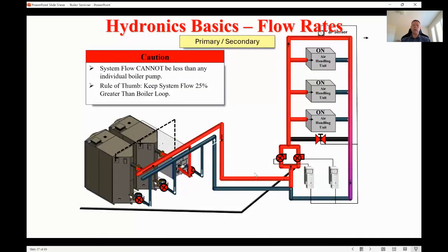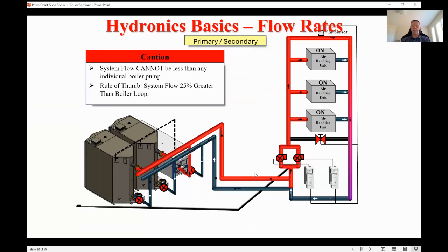So one of the things you've got to watch with primary, secondary piping is you always want to have more flow in the system loop, or the secondary loop, than you do in the boiler loop, or the primary loop. Let's say you have a system like this. Let's say you have 3 zones here. We've got a few boilers and a few VFDs, right? Because if something spins now, you have to put a VFD on it. Let's say as these zones close and these air handlers shut down, you'll find, okay, something's shutting off. The pressure's building up now, that zone's closed. So I'm going to start ramping that pump down.